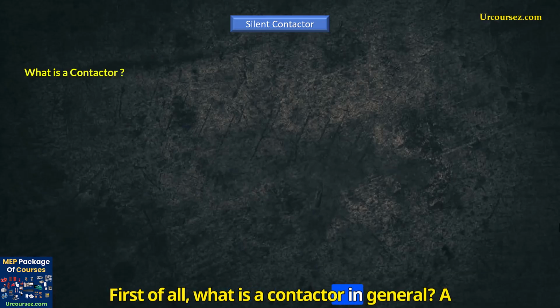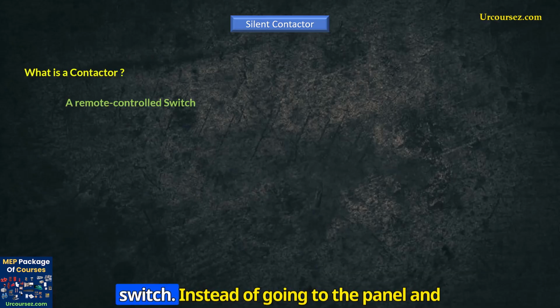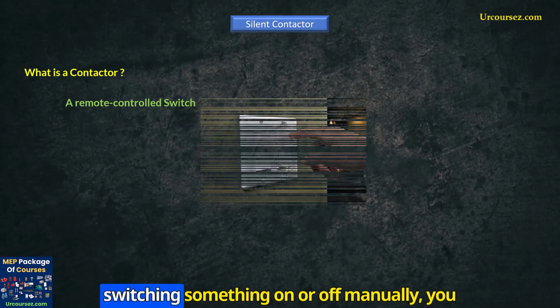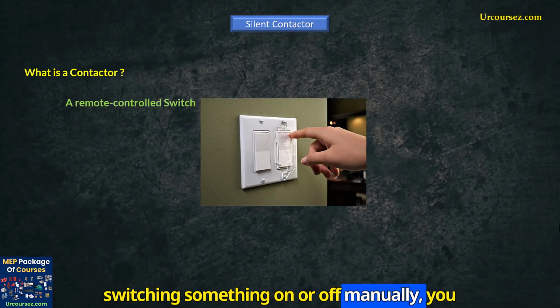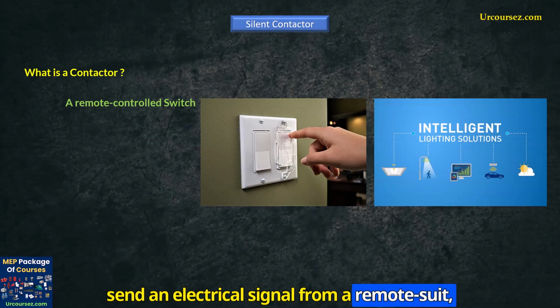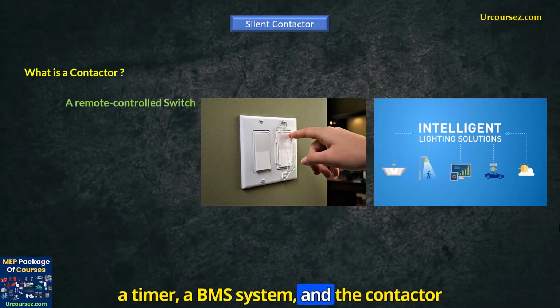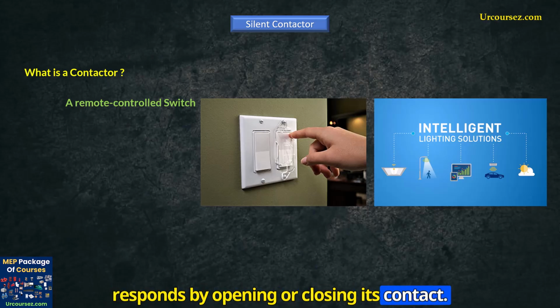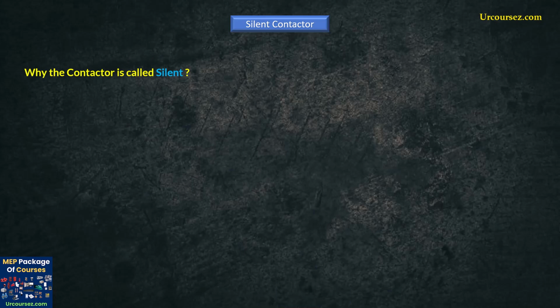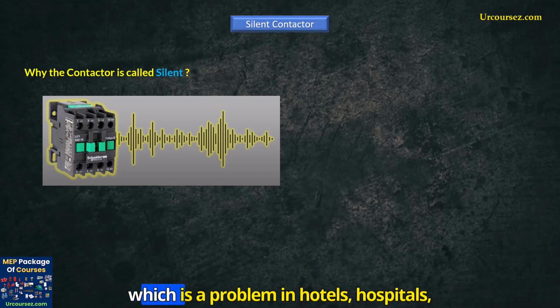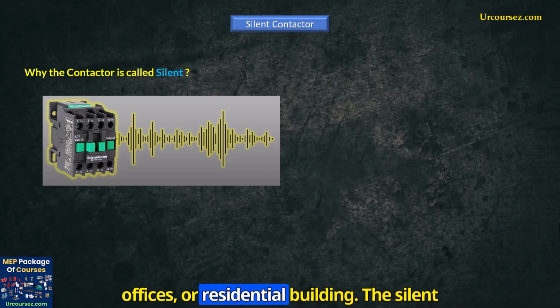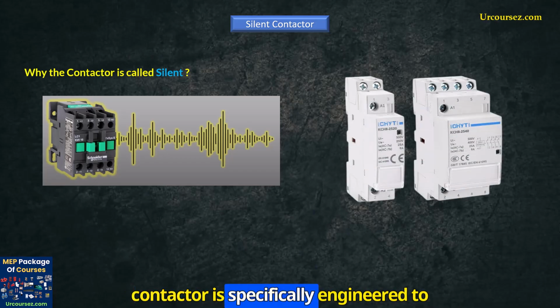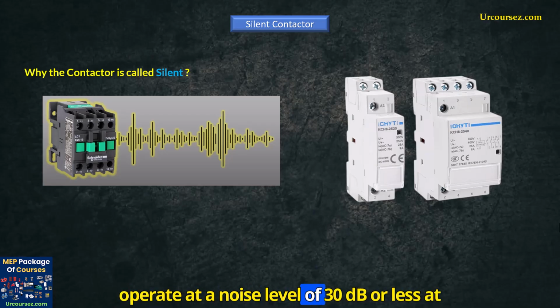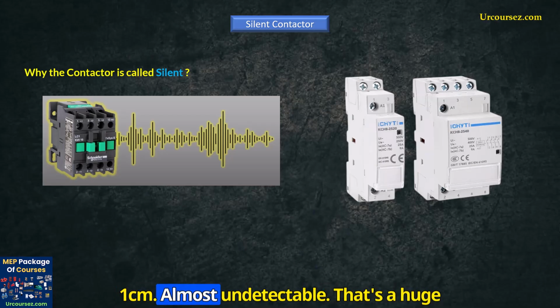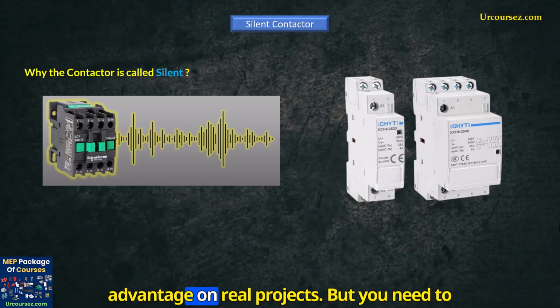First of all, what is a contactor in general? A contactor is simply a remote-controlled switch. Instead of going to the panel and switching something on or off manually, you send an electrical signal from a remote switch, a timer, or a BMS system, and the contactor responds by opening or closing its contacts. Now, why silent? Because traditional contactors make a loud clicking or buzzing noise when they operate, which is a problem in hotels, hospitals, offices, or residential buildings. The silent contactor is specifically engineered to operate at a noise level of 30 dB or less at 1 centimeter, almost undetectable. That's a huge advantage on real projects.